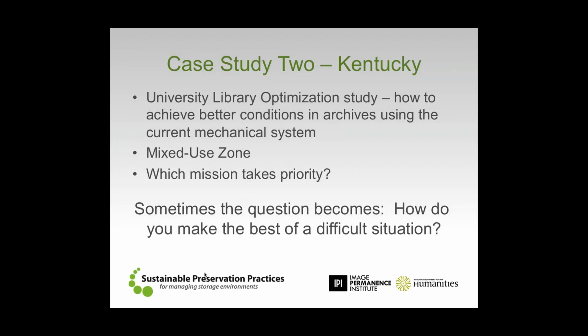Now, what it comes down to is that means that the system all the time is going to have to cool in order to meet what needs to be done in the archives on the lower floor. But in addition to that cooling, now you have to reheat a portion of that air significantly back up to 70 degrees in order to achieve what the technical services space needs.